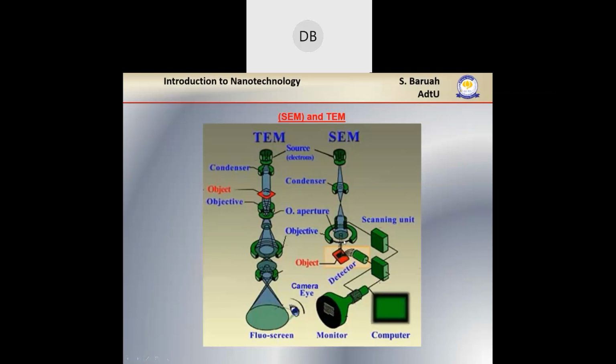If we have more backscattered electrons coming out from your sample, then the backscattered electron detector will give a better image. And if there are more secondary electrons coming out from the sample, then your secondary image detector will give you a better image. So ultimately, it's again the variation of intensity. Based on the intensity of those individual electrons when they hit the detector, we get different images.